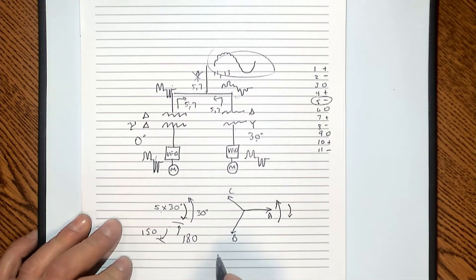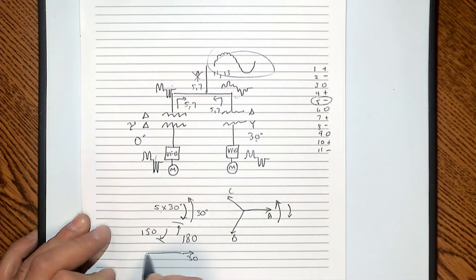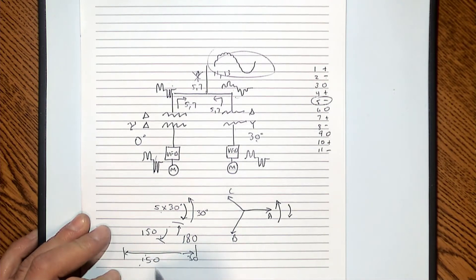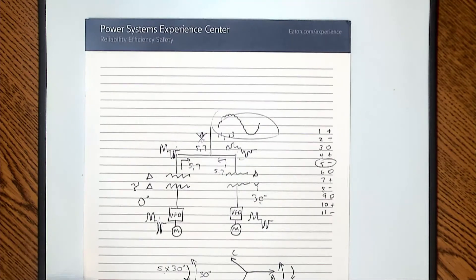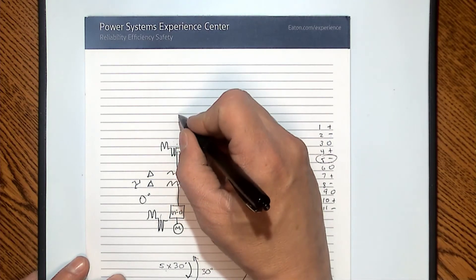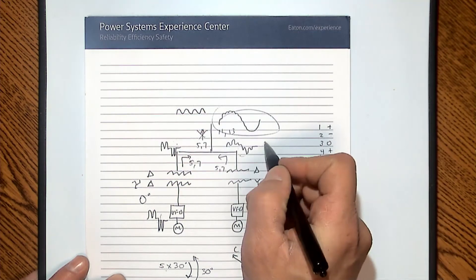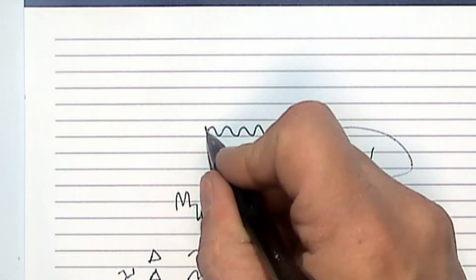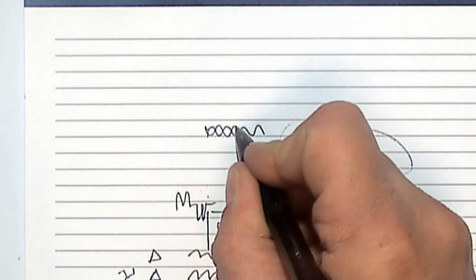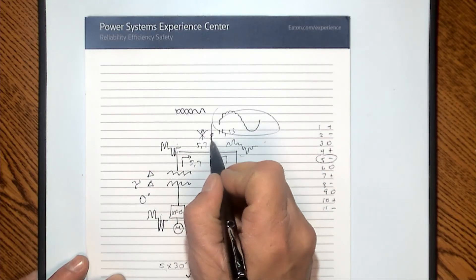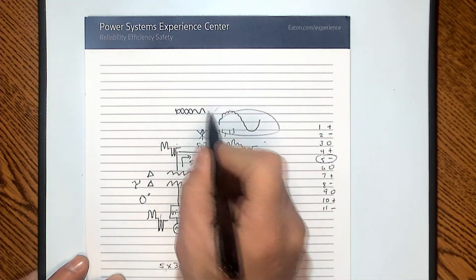It's like two vehicles leaving at the same time going opposite directions — one goes 30 miles this way, the other goes 150 miles that way; the difference is 180 miles. In this case, we're 180 degrees out of phase. So when the fifth harmonic comes up from the bottom on one side, it's a certain waveform, and when the fifth harmonic comes up from the other side, it's exactly the opposite. Those two added together in the upstream path go to zero.